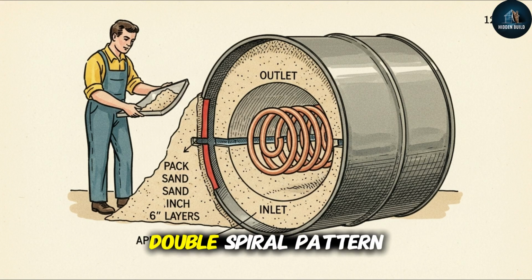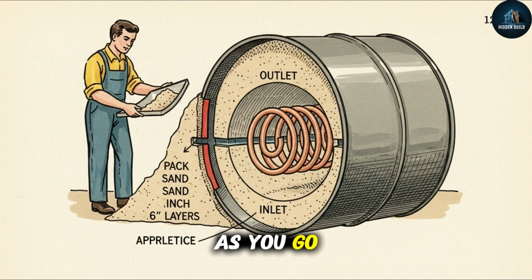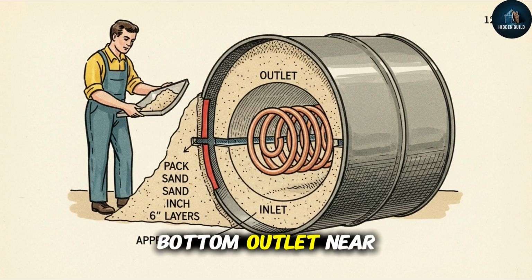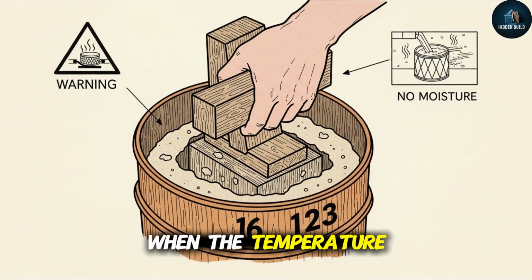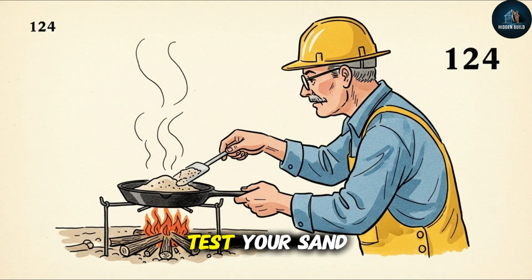Here is the construction sequence. Pack the drum in 6-in layers, laying the copper coil in a double spiral pattern as you go. Inlet at the bottom, outlet near the top. Leave no air pockets. Dry sand only. Any moisture will flash to steam when the temperature rises and create pressure inside the drum. Test your sand by heating a small sample in a skillet. No sizzle or steam means it is ready.